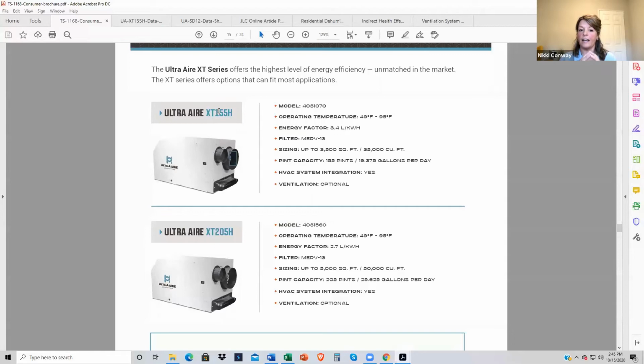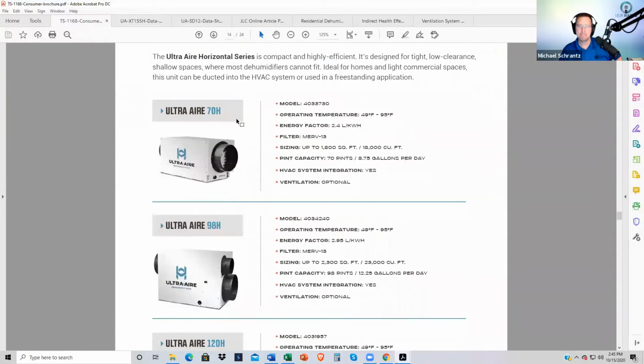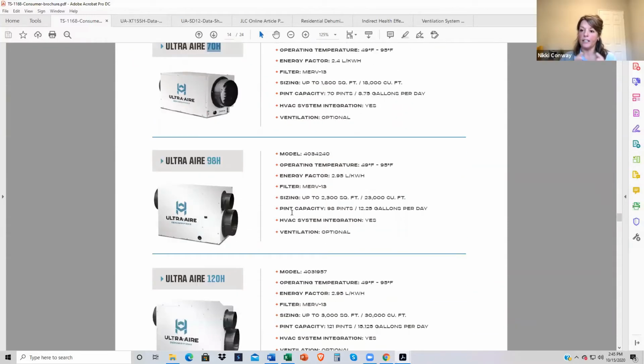So let's say, to make it simple, the 70 pint unit is 150 CFM. The max ventilation we can get from the unit is 1/3 of the total CFM - that's 50 CFM. We can get 50 CFM of ventilation air from that smaller 70 pint unit.